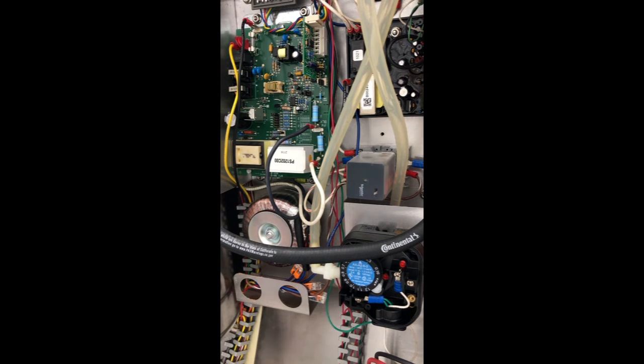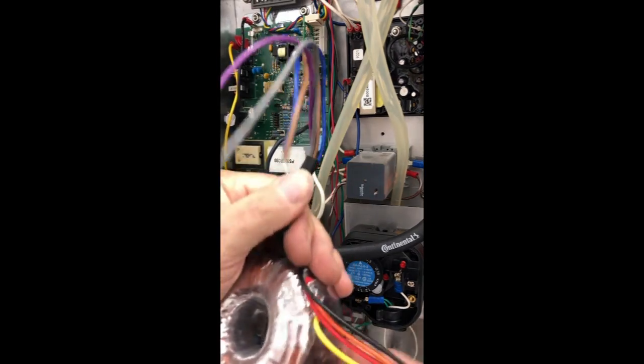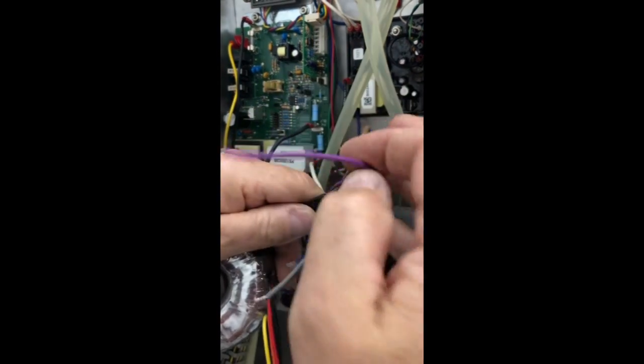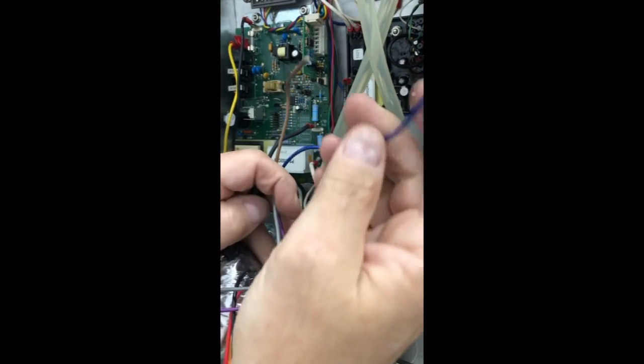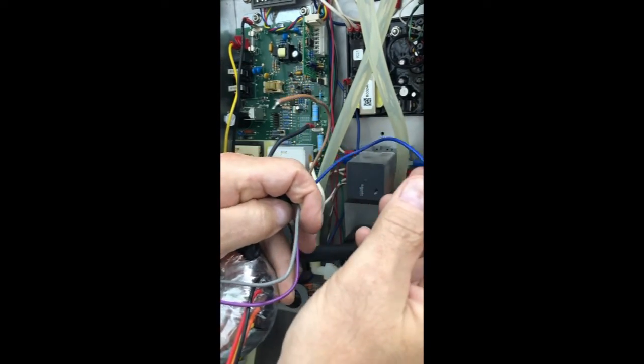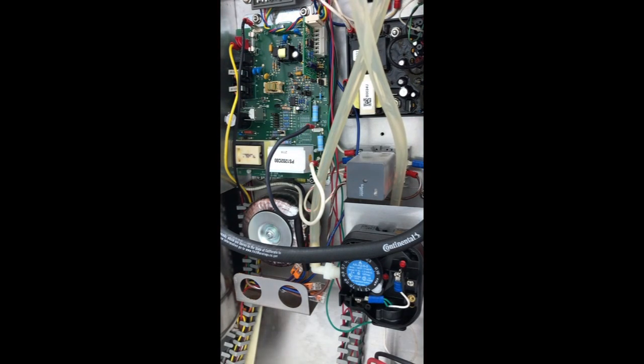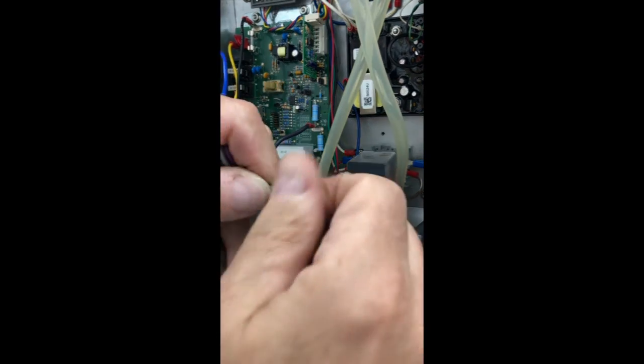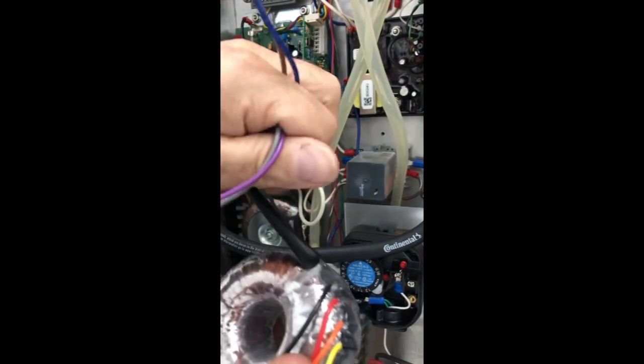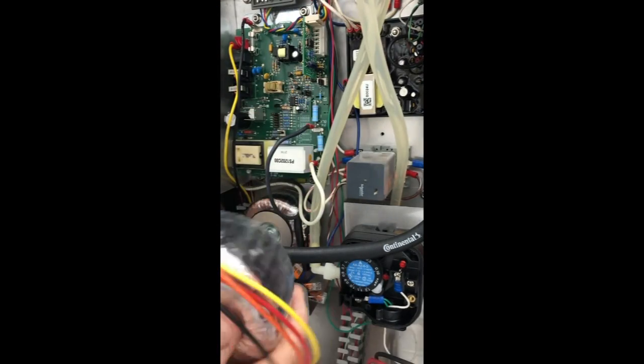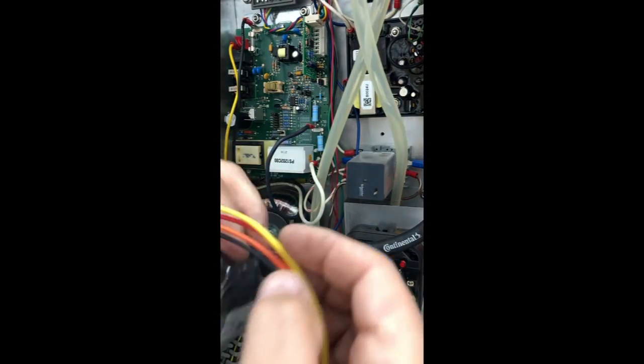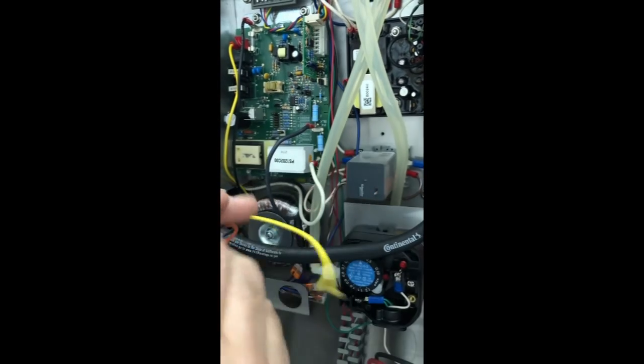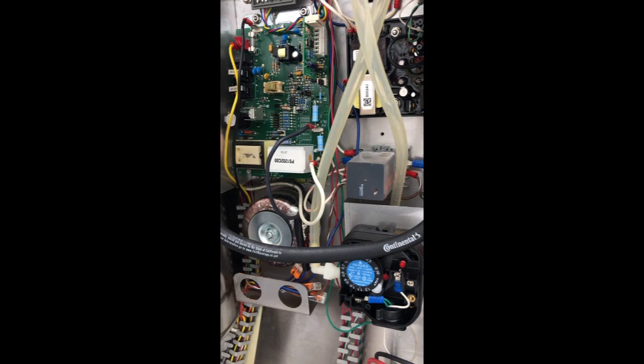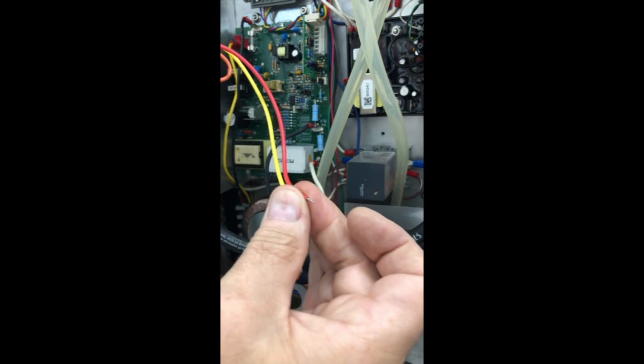That works fairly well. When you go to wire your transformer, you're going to get your transformer like this. The blue and the brown, those are your high voltage leads. That's going to be your 208 or 240. These two leads, we're going to tie those two together. Okay, just put a Marrette or a wire nut on there. So now here's your incoming leads. On the outgoing, I always remember Halloween. So it's orange and black go together. Okay, and then they're going to go to either P1 or P2. And then yellow and red go together, and they'll go to P1, P2.